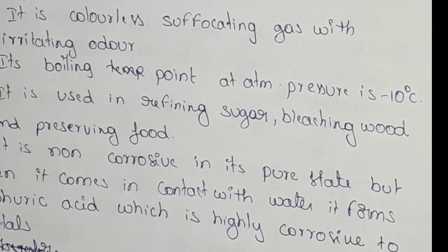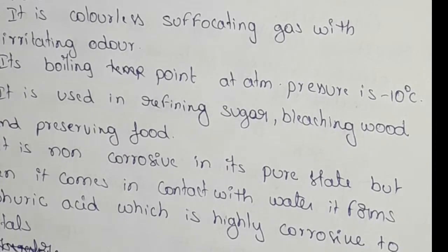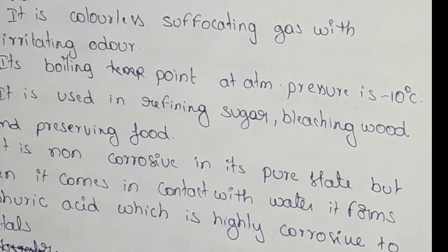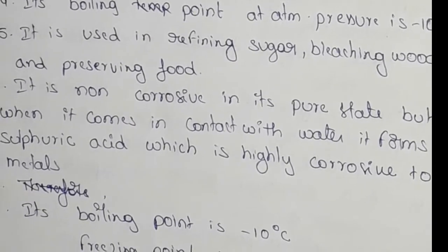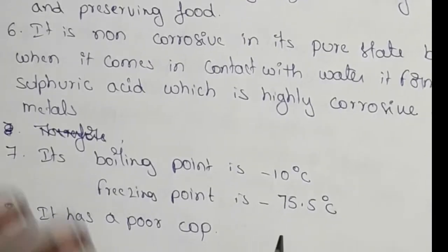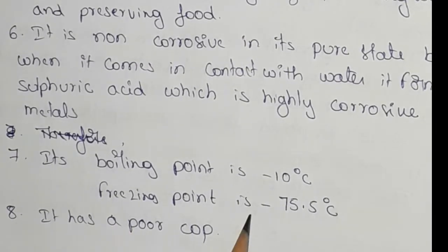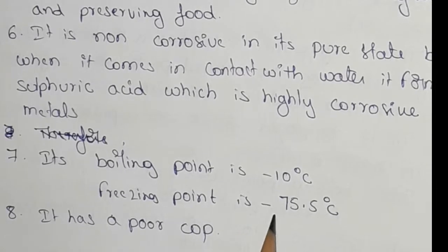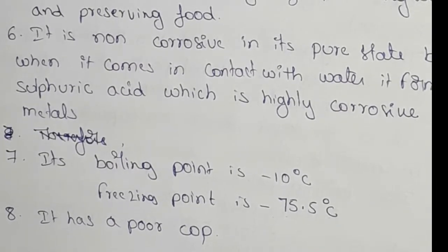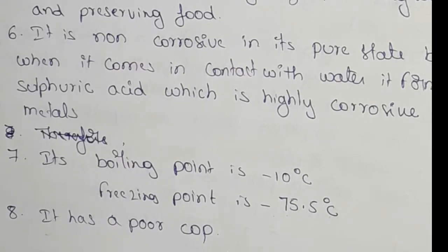When it forms sulfuric acid, it becomes highly corrosive to metals. The boiling point is minus 10 degree centigrade and the freezing point is minus 75.5 degree centigrade. It has a poor COP.